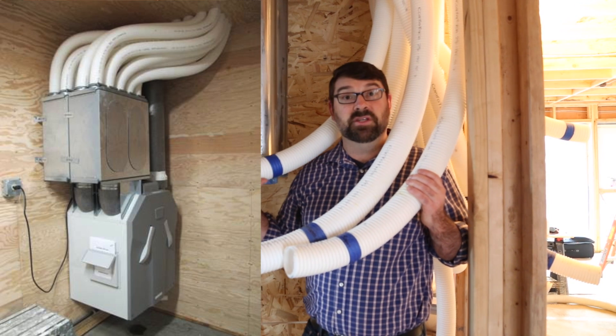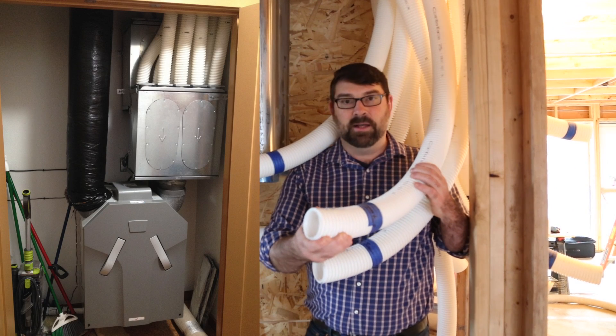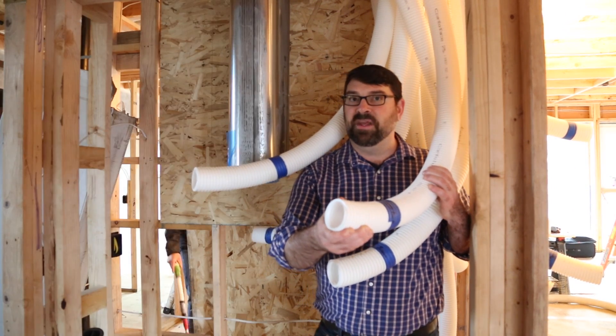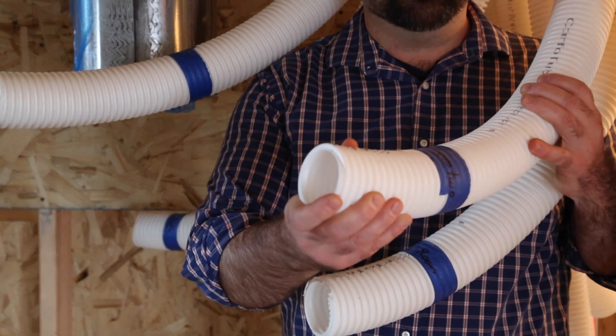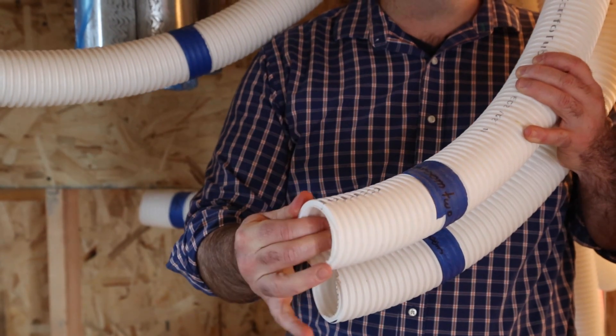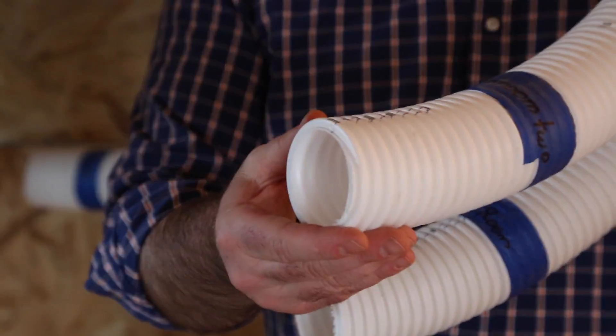The distribution ducts for this Zehnder system are these little tubes called Comfo Tubes — each three inch round. They're corrugated on the outside, which gives them strength and rigidity, but smooth on the inside, so there is very low resistance to airflow through them.